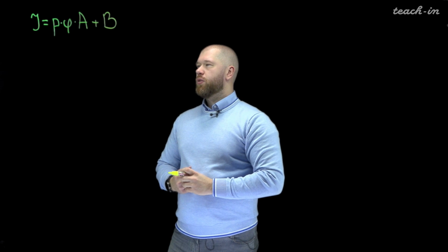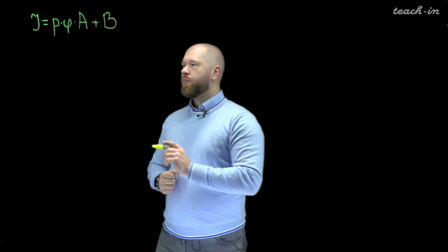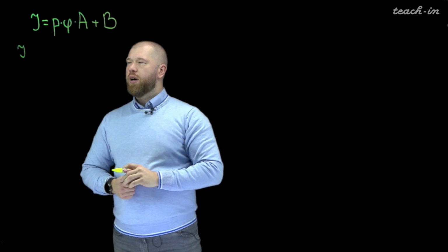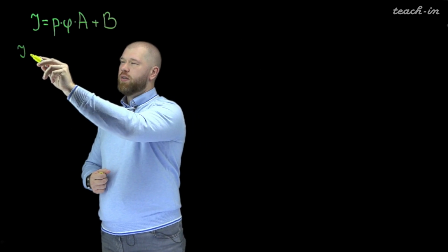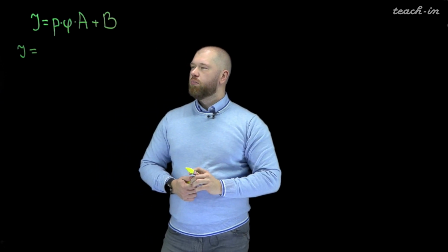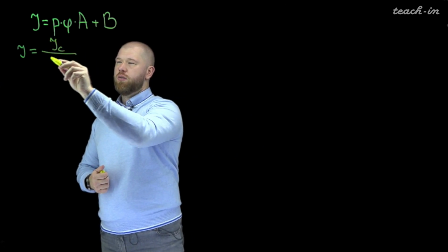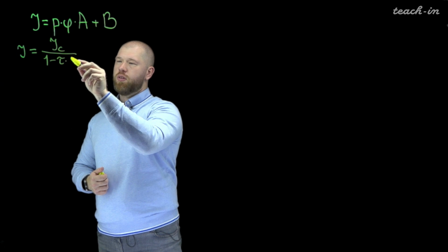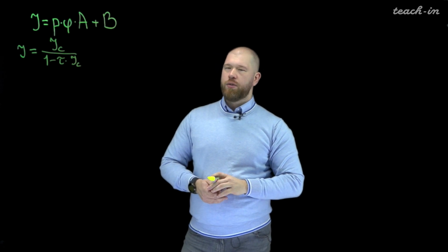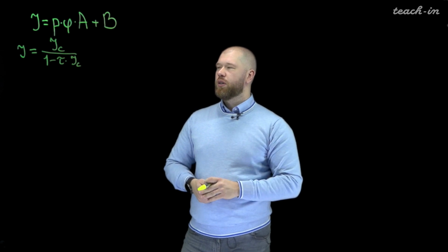When we would like to calculate the absolute activity, we also have to have in mind that the real count rate depends on the measured count rate with this ratio, where this tau letter means the dead time, that is a specific parameter for a detector.